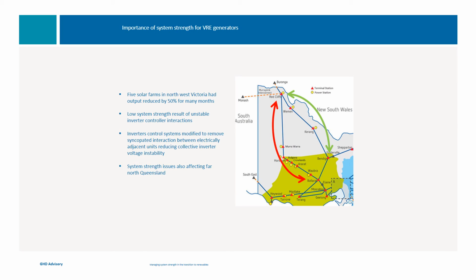A number of speakers have already talked about the system strength related constraints placed on VRE connected to the Redcliffe to Horsham to Ballarat line in northwest Victoria. The main point I would like to make with regard to this is that the issue was resolved in part through improvements in the inverter software control systems and settings. And indeed, one of the recommendations of our report is that the better approach to resolving the system strength issue is not to continue with the palliative response to system strength by installing synchronous condensers, but to address the root cause and work with inverter manufacturers to improve their control systems such that inverters don't detract from system strength, but perhaps can support it.